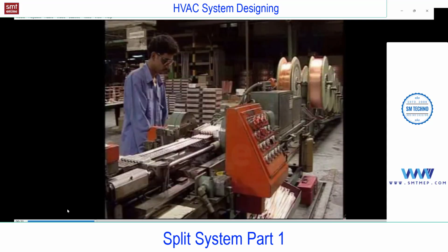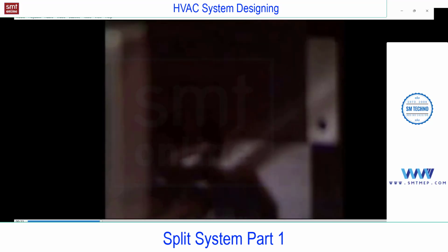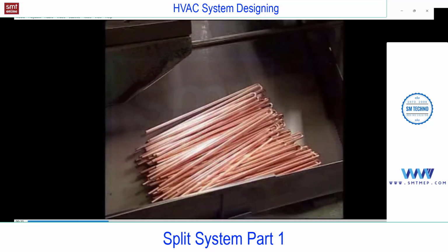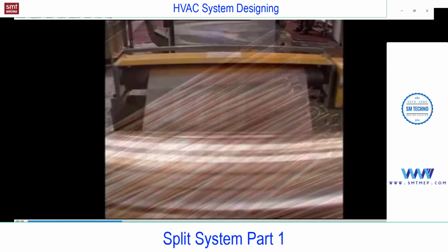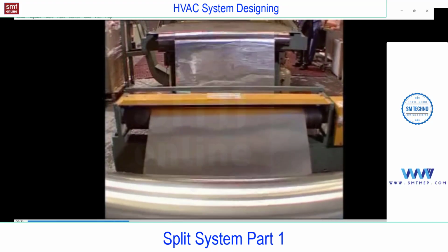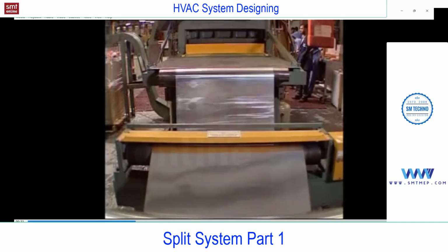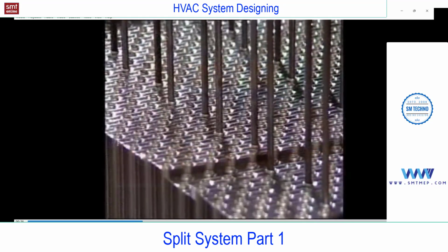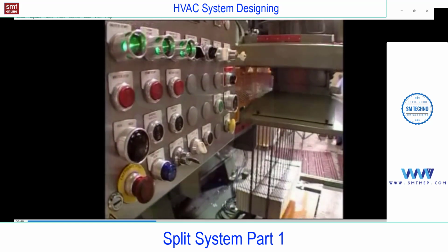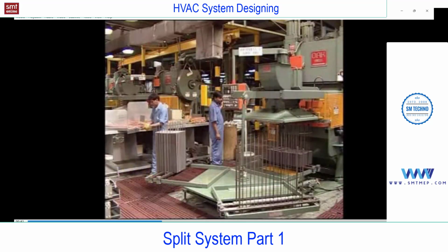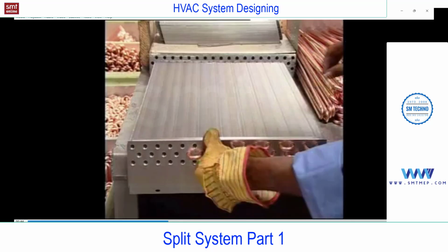Hairpin tube cutting and bending machines, which draws the tubes from the copper reels, cuts them to the required length and bends them 180 degrees. Alongside is the fin pressing, where the punching of holes, corrugating of the surface and cutting to the required dimension takes place. Fins are then collected, end plates attached and hairpin tubes inserted, thus forming the heat.